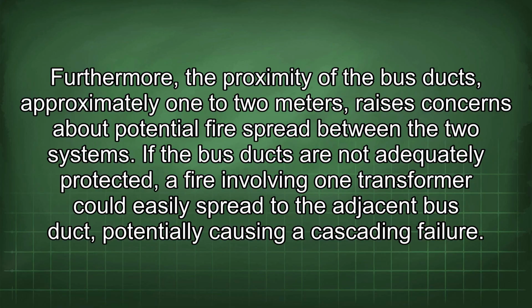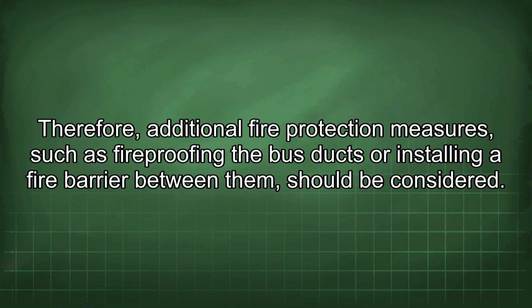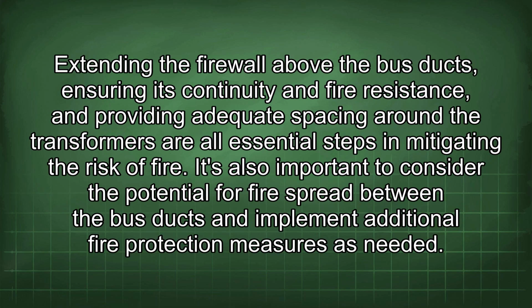If the bus ducts are not adequately protected, a fire involving one transformer could easily spread to the adjacent bus duct, potentially causing a cascading failure. Therefore, additional fire protection measures, such as fireproofing the bus ducts or installing a fire barrier between them, should be considered. To summarize, while the existing oil collection pit with fire-quenching stones provides a level of fire protection, it is crucial to ensure that the firewall meets the requirements of IEEE 979 and is properly designed and maintained to prevent the spread of fire. Extending the firewall above the bus ducts, ensuring its continuity and fire resistance, and providing adequate spacing around the transformers are all essential steps in mitigating the risk of fire.